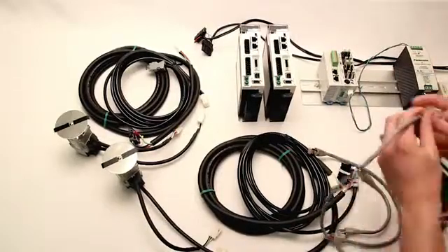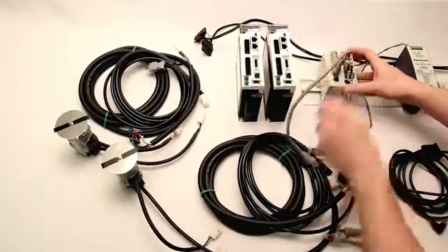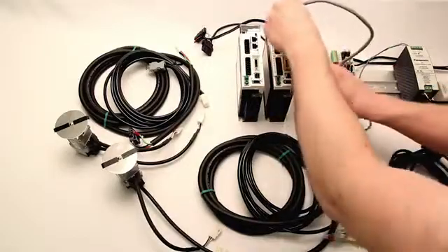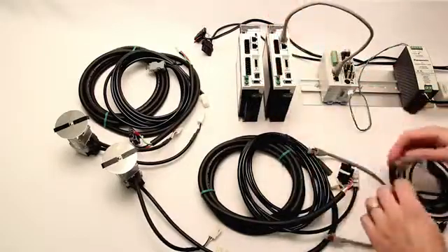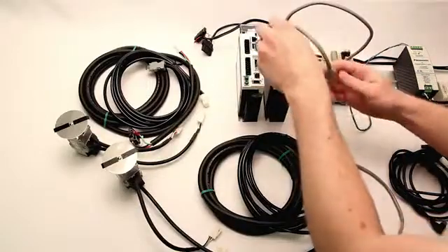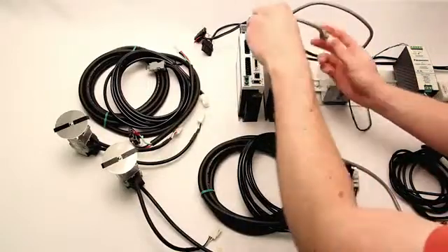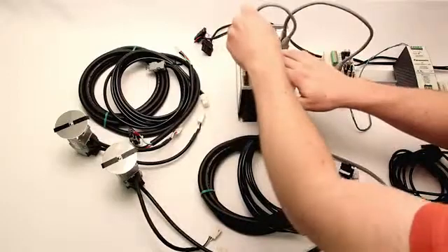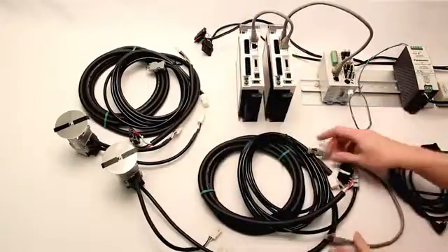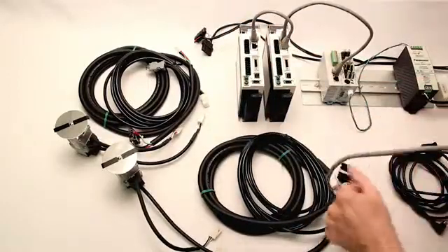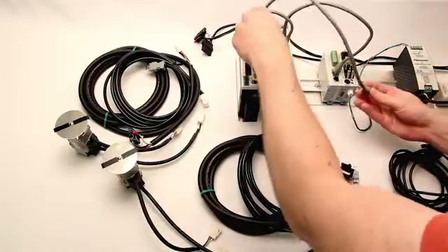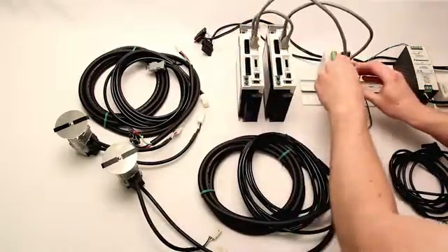Now it's a very simple ring topology. I'll use the transmit of the PLC and put that to the receive of the first drive. And then the transmit of the first drive to the receive of the second drive. And lastly, I will take the transmit of the second drive and put it to the receive of the PLC.